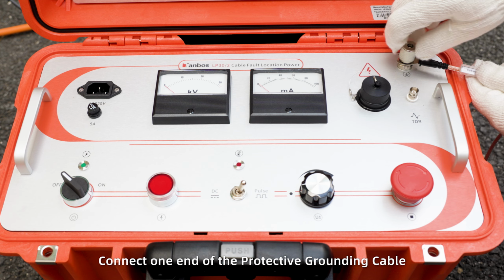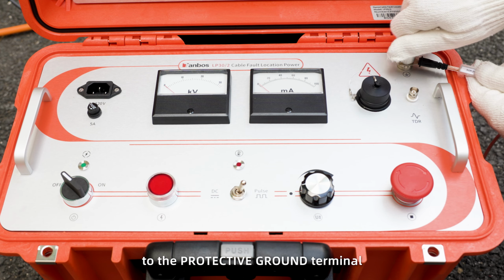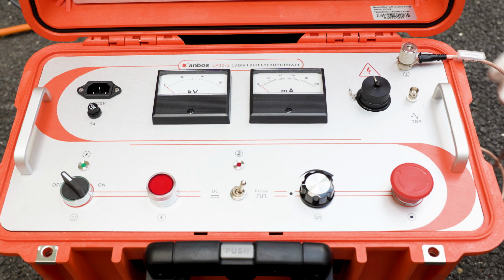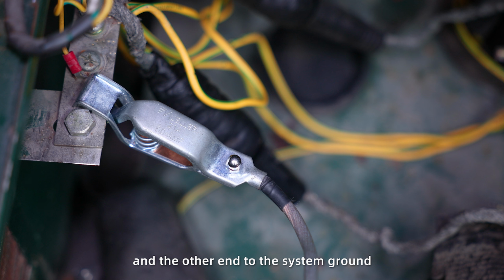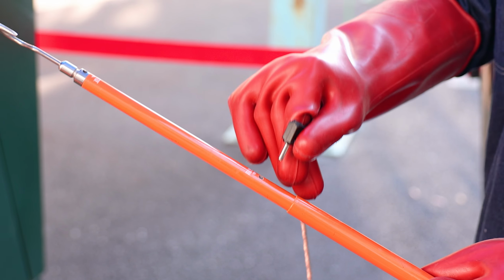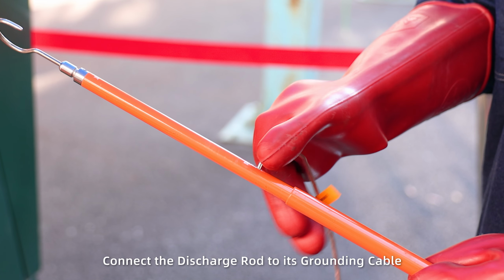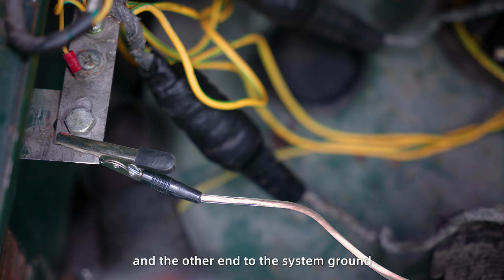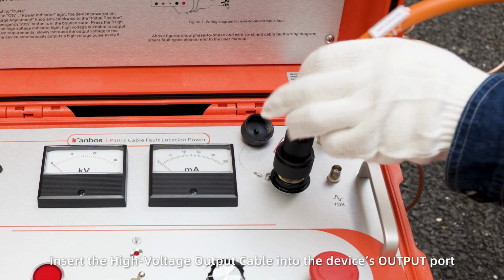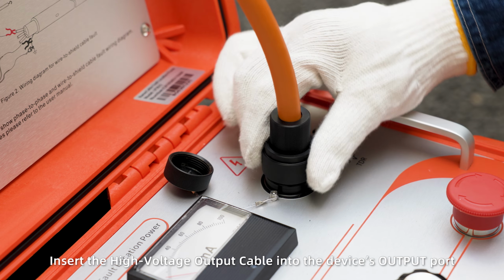Connect one end of the protective grounding cable to the protective ground terminal and the other end to the system ground. Connect the discharge rod to its grounding cable and the other end to the system ground. Insert the high voltage output cable into the device's output port.